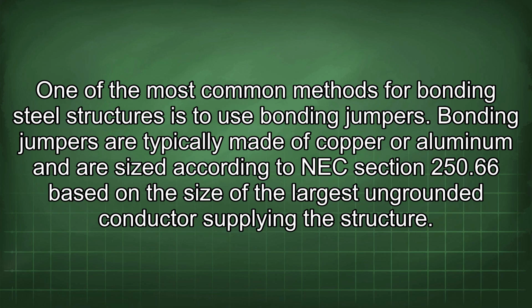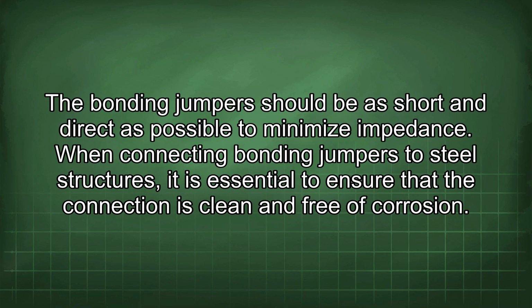One of the most common methods for bonding steel structures is to use bonding jumpers. Bonding jumpers are typically made of copper or aluminum and are sized according to NEC section 250.66 based on the size of the largest ungrounded conductor supplying the structure. The bonding jumper should be as short and direct as possible to minimize impedance.